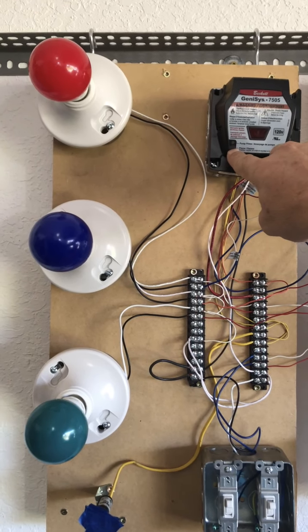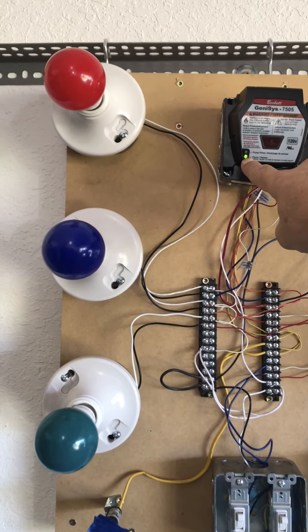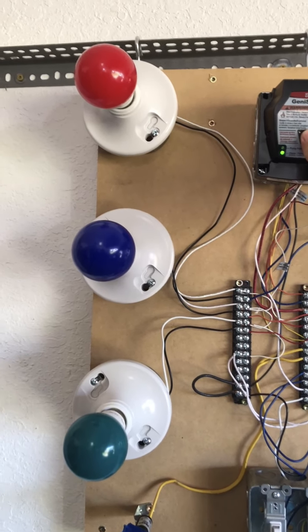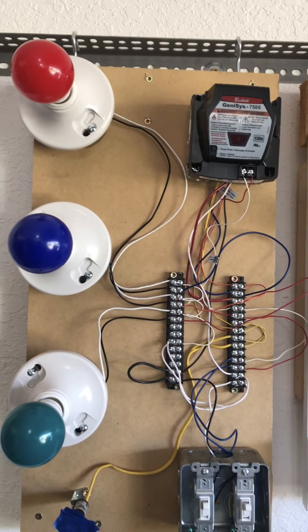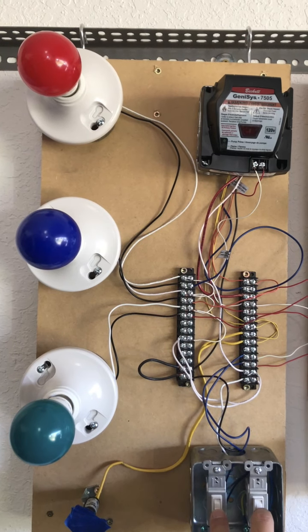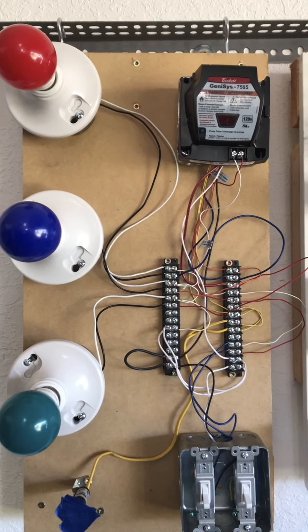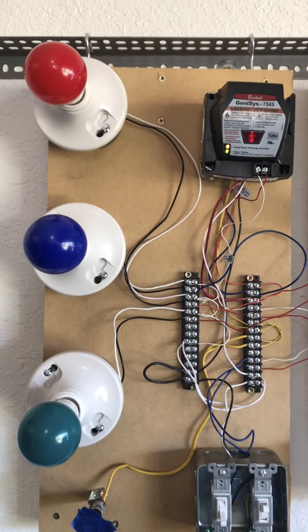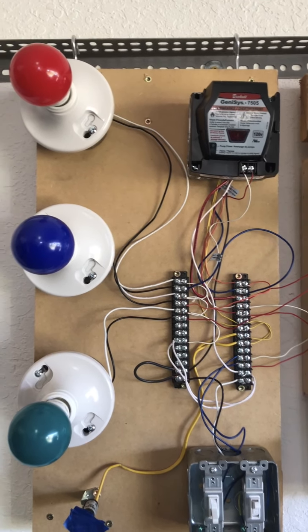And we have my blinking light up here that says flame has gone out and we need to recycle this control. Now this control does not have a reset button on it any place. So what we basically do is turn power off, and we can turn the power back on and try another cycle.